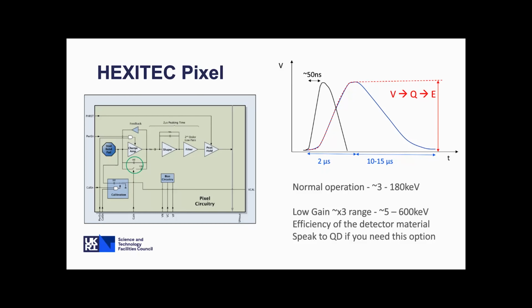To get a clean signal, we want to shape and filter that pulse, and we use a second order filter here. This is just a standard RC/CR shaper, and it has a peaking time of about 2 microseconds. So that tracks the output of the amplifier and gives us this nice smooth rising edge, this blue trace here, and that's connected to a peak hold. The peak hold tracks that level and stores this voltage level. So that's giving us that measurement of the voltage, which gives us the charge, which gives us the energy.